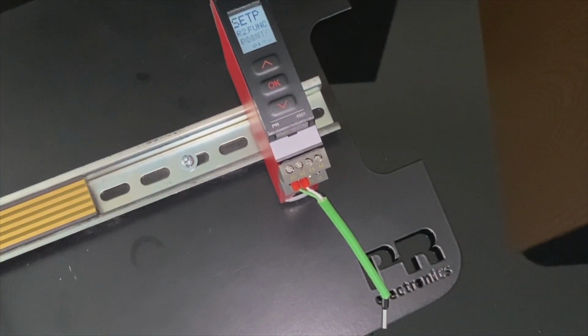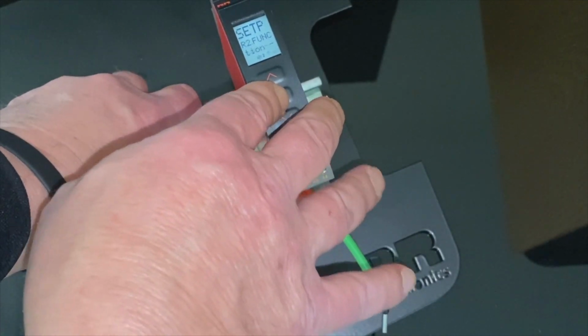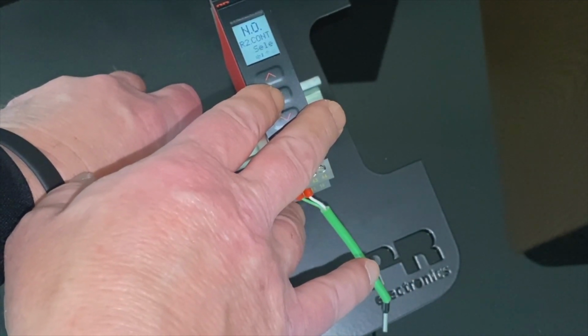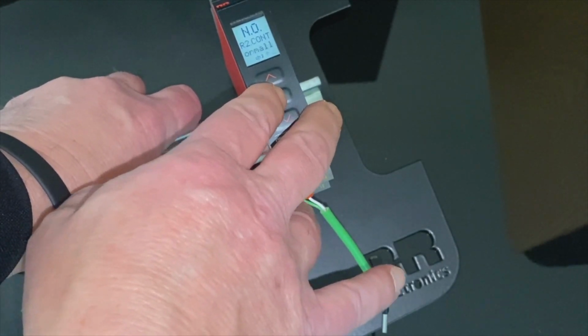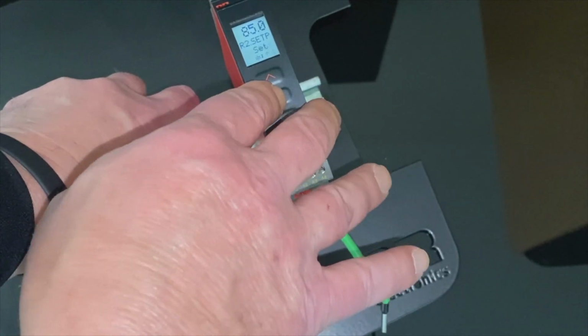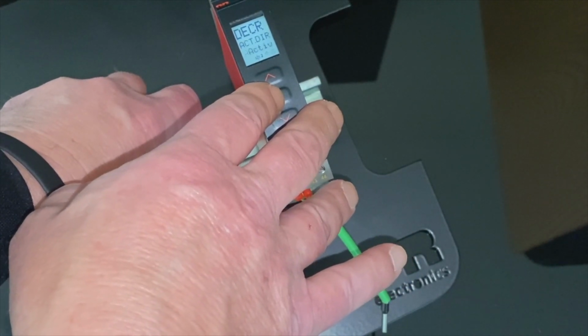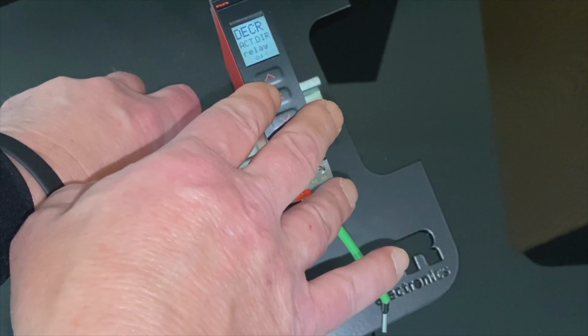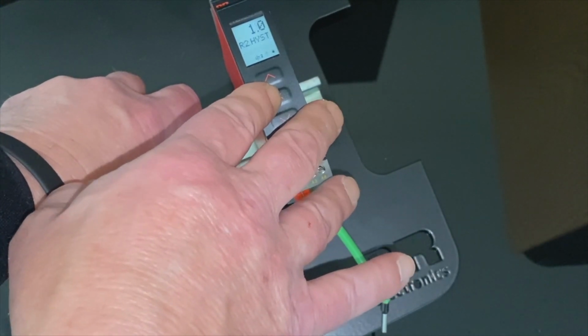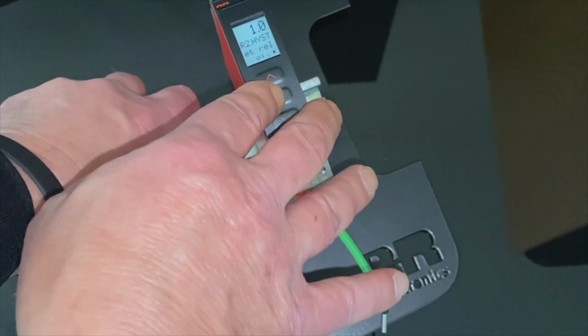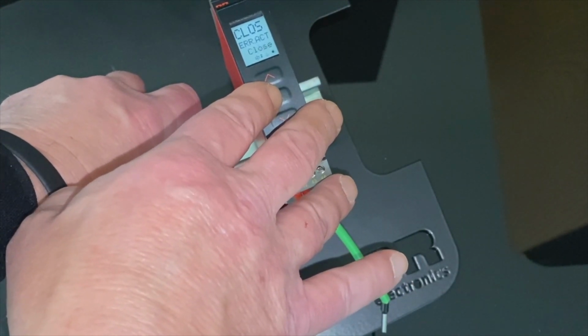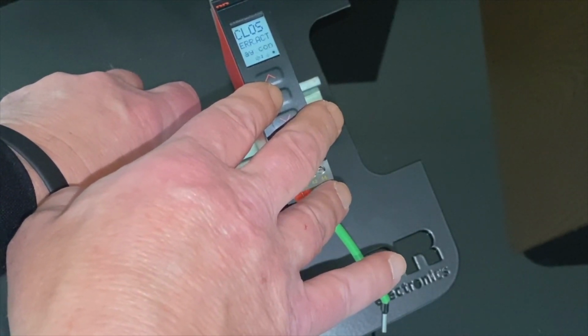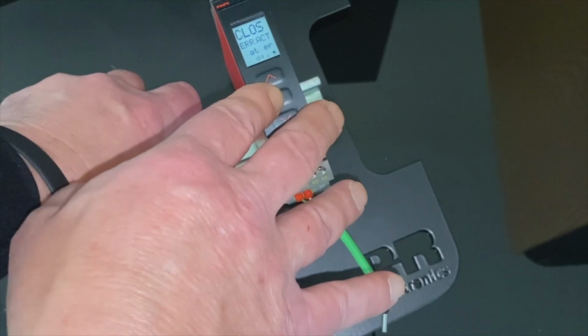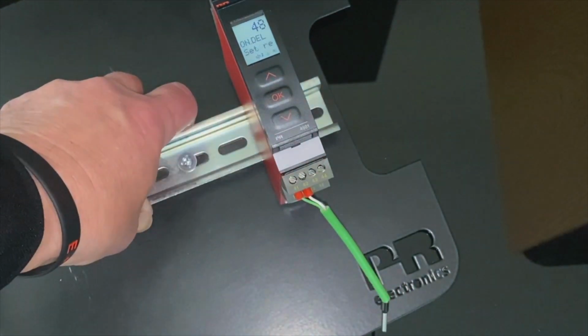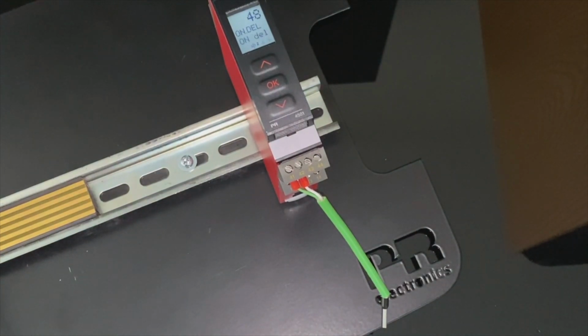In relay 2, the set point function is one of the most commonly used functions. So you first put your set point function in. You select normally open or normally closed. You enter your value. Now, do you want that relay to engage when the value is going down or up? So you either select increasing or decreasing. Your customer can add a hysteresis. What do you want to happen if there's an error in the system? What do you want the relay to do? Open, close, or do nothing? So you select that. And there's also a timer that you can program from 0 to 1 hour, 60 minutes.